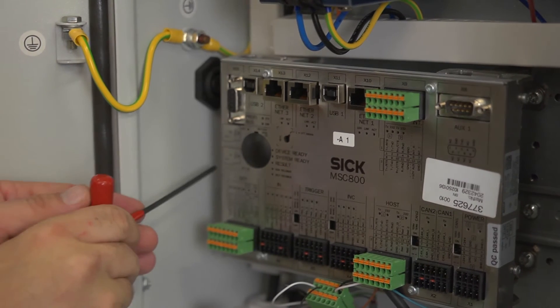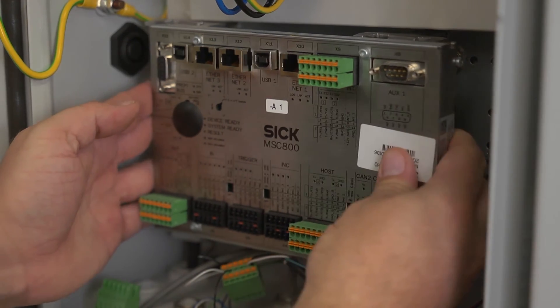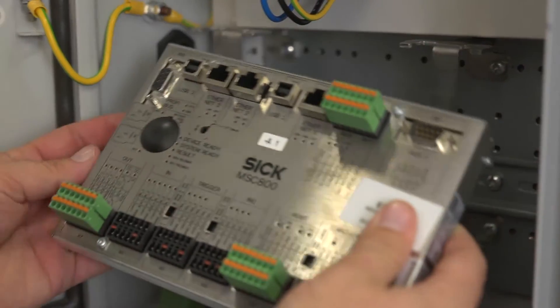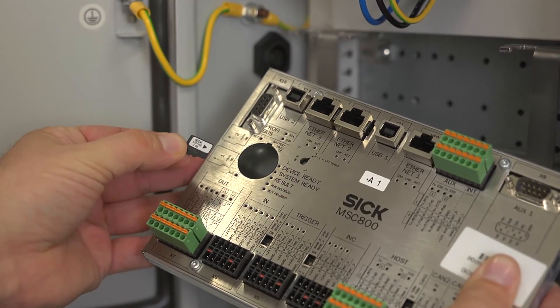Loosen the three millimeter fastening screw on the left-hand side of the MSC and slide the controller out towards the right. Remove the SD memory card, which contains the saved parameter set, from the defective MSC controller.